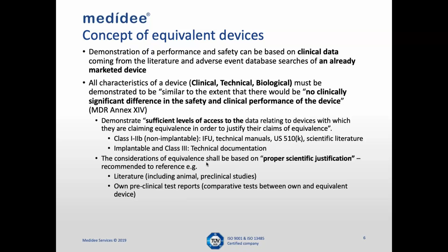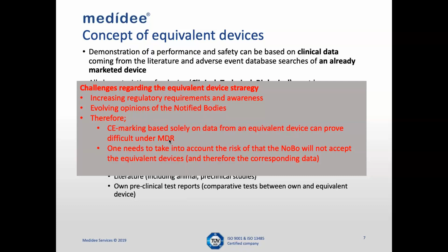But at the end of the day, this strategy is very challenging, mainly because of the increasing regulatory requirements and the awareness, and also the evolving opinion of the notified bodies. Because at the end of the day, it's the notified body who's going to decide whether to accept or not accept the claimed equivalent device. And it can be a risky process if you're not absolutely confident that you have an equivalent device which will be accepted by the notified body. So currently, CE marking based solely on data from equivalent devices can prove pretty difficult under MDR. So it is recommended to also utilize other sources of clinical data.